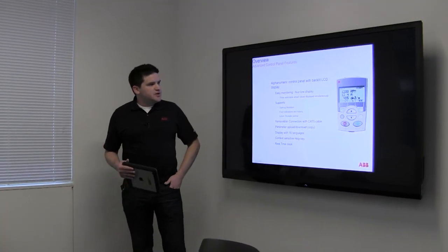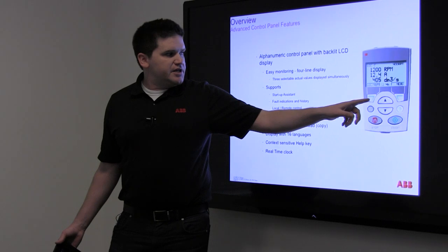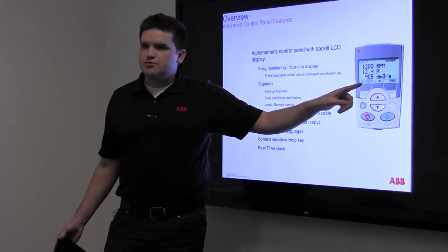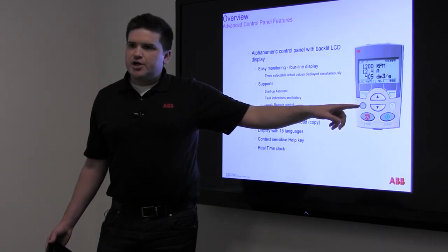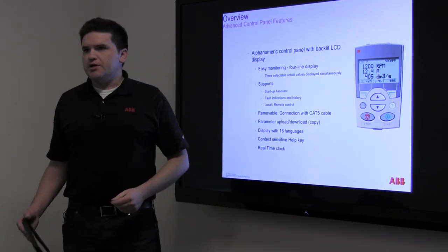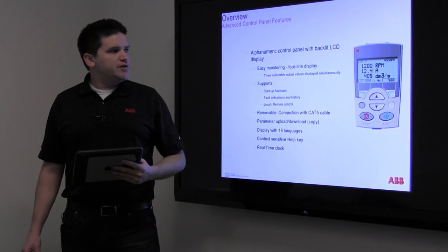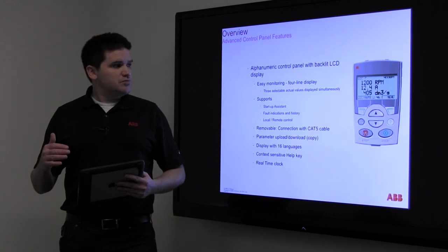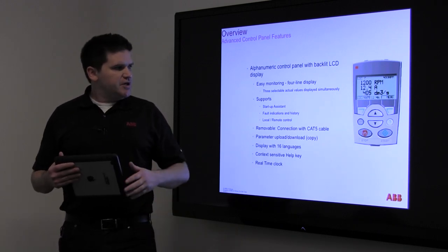This is the advanced control panel. These two buttons are called soft keys — they change function corresponding to whatever is on the actual readout. The rest are self-explanatory. This is your hand/auto button. If you hit it, it'll say 'hand,' which means it's no longer being controlled by the BMS. In auto, it is being controlled by the BMS. Sometimes the setup requires you to go in and change a parameter before you can put it in hand mode — it depends on the configuration.